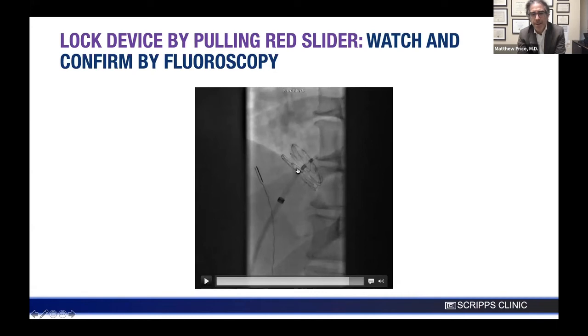You see a couple of things happen. Number one, that black line disappears. Number two, the eyelets loosen up a little bit. That's normal because what's happening is this device is conforming to the interatrial septum with limited tension. That's what you want. Third is you see the device has moved a little bit away from our delivery catheter. That's because it's no longer connected by rigid nitinol. It's only connected to our delivery system by the suture retrieval cord.